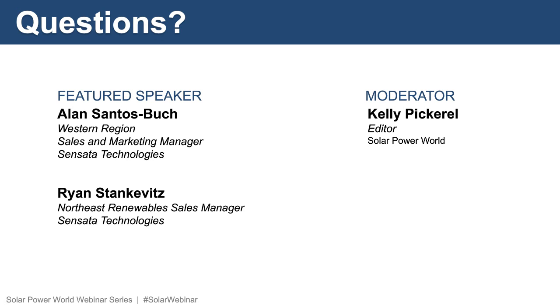Okay. Thank you. So does the Micro GT have rapid shutdown built in, or does it still require a disconnect switch at ground level? I'll grab this one, Kelly, because it sort of applies to the question 3. Similar to what we talked about a couple questions ago, the Micro GT is basically an AC. It produces AC outside the inverter, so it doesn't really qualify for rapid shutdown, if you will. But again, as I mentioned before, some inspectors do still consider that and want to see an initiator, if you will, or a disconnect.